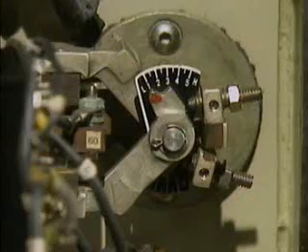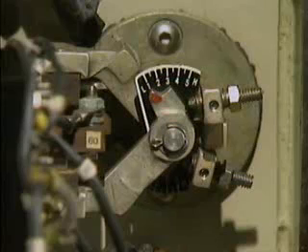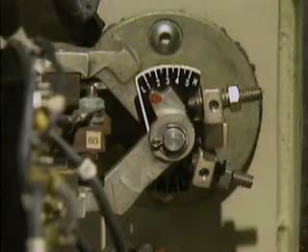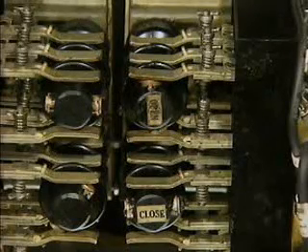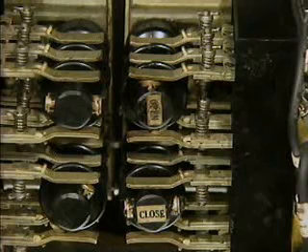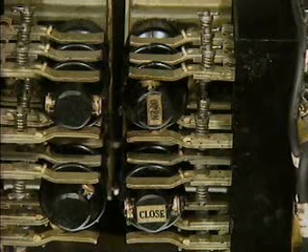This is a torque switch. Basically, torque is a turning or twisting force. A torque switch cuts off electric current when the amount of turning force caused by the motor reaches a preset limit. This is a limit switch. It cuts off electric current to the motor when the valve reaches a preset position.